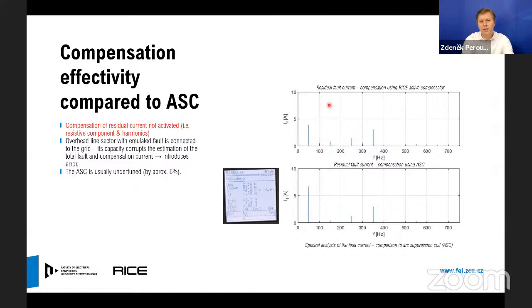As I explained, we identify the grid impedance in real time under no-fault conditions. So we were unable to exactly identify the total grid impedance due to this missing part of the grid. Therefore, our compensation current was not fully optimal. Even under these unfair conditions, our device, this is the upper figure, significantly outperformed the arc suppression coil. The final current was half of the residual current for the optimally tuned arc suppression coil.